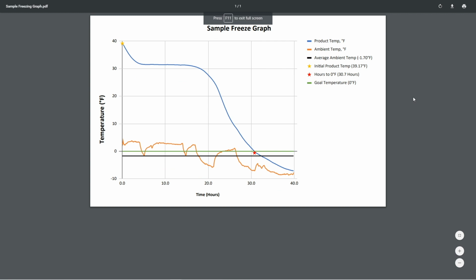Now, lastly, I'm going to show you a typical freeze curve. This was recently done in a customer's facility, but this is a very typical freeze curve where we're plotting the gold line, which is the room temp or ambient temperature. The blue line is an internal product probe. So the initial product temp here was 39.17, and notice the sensible heat above freezing comes out rather quickly. And that's pretty much this run right here.